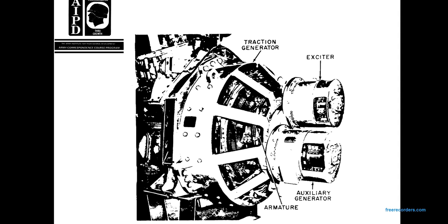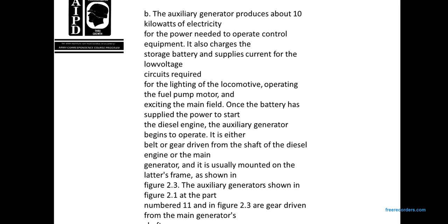This is a traction generator, an exciter, and an auxiliary generator with armature. The auxiliary generator produces 10 kilowatts of electricity for the power needed to operate the equipment. It also charges the storage battery, supplies the current for the low voltage circuit required for lighting the locomotive, operates the fuel pump of the motor, and excites the main field.